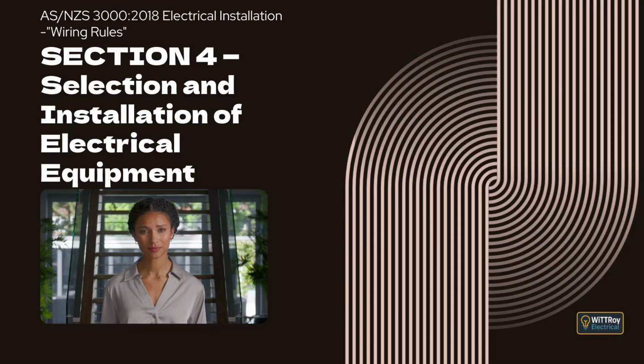Clause 4.9. Room heaters. This clause introduces requirements for permanently connected room heaters. Clause 4.9.1. General. This clause explains that where one or more permanently connected room heaters are installed in a room, each room heater, or each group of room heaters, must be provided with an individual isolating switch and an individual functional switch. It explains that where multiple room heaters in one room are supplied by the same final subcircuit, a single isolating switch may be used for that room.